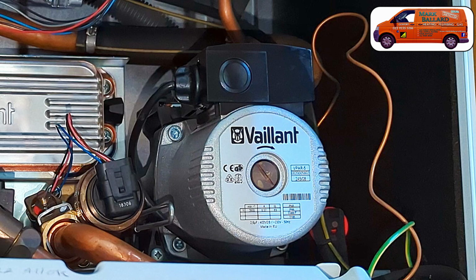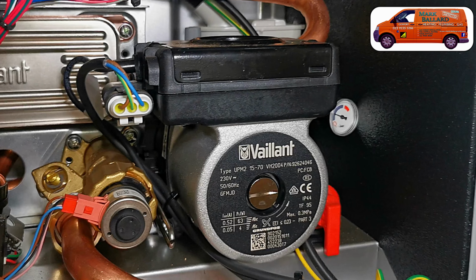description. Now, just before I get on with it, if you are unlucky enough to have a faulty pump and you need to replace it, I want to let you know that with the older boilers, they had a slightly different pump to the newer boilers, and Vaillant have now replaced that older pump with the newer pump, and you'll need to buy the pump plus an adapter lead to fit onto your boiler.